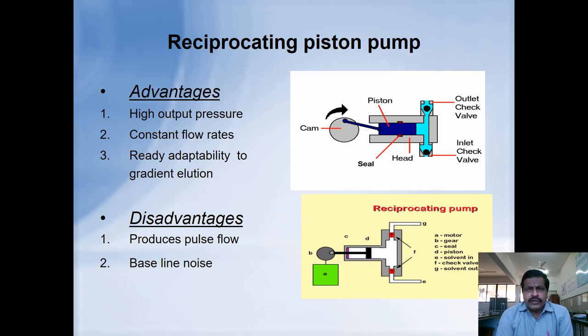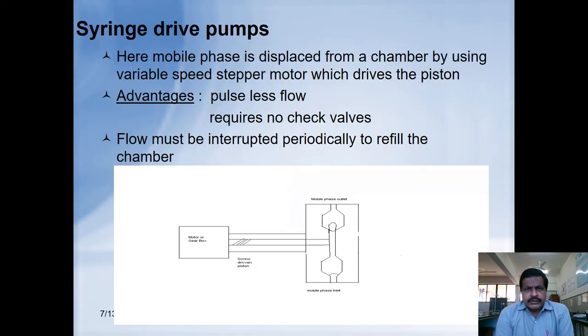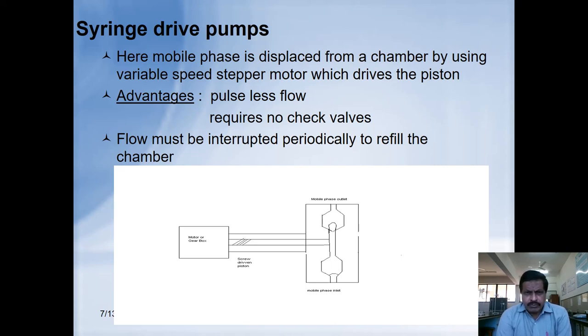This is a schematic representation of a reciprocating piston pump. Its advantages include high output pressure, constant flow rates, and it is readily adaptable to a gradient elution system. A disadvantage is that it produces pulsed flow and there may be baseline noise. The second type is the syringe drive pump, where the mobile phase is displaced from a chamber using a variable-speed stepper motor which drives the piston. It is pulse-less and requires no check valves, but the flow must be interrupted periodically to refill the chamber.